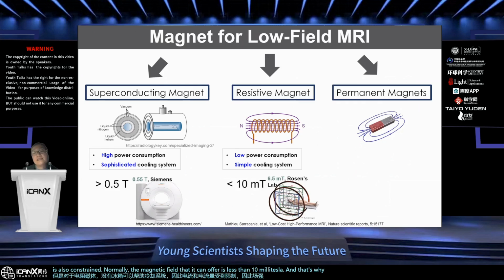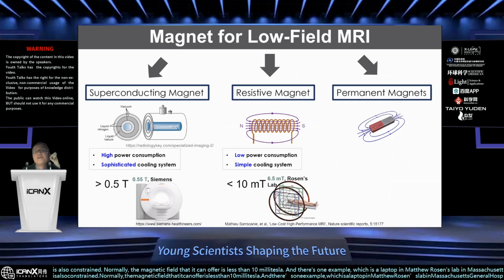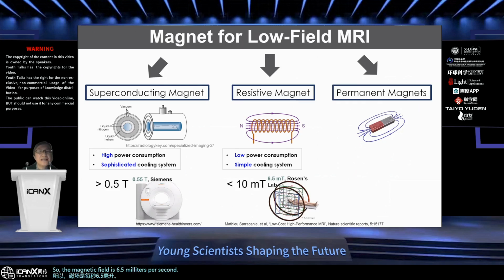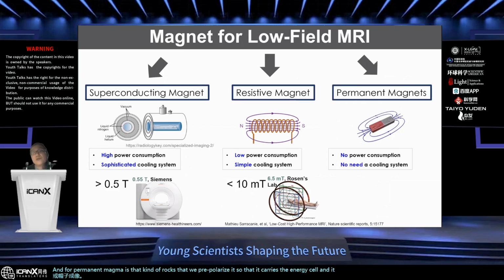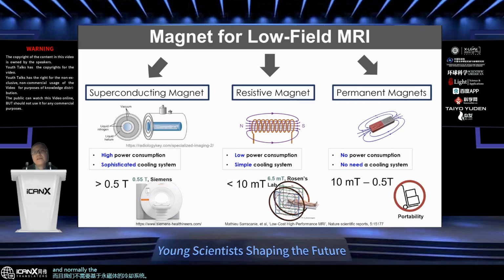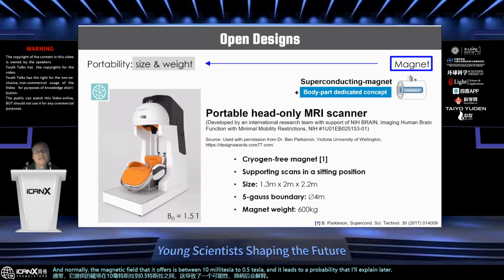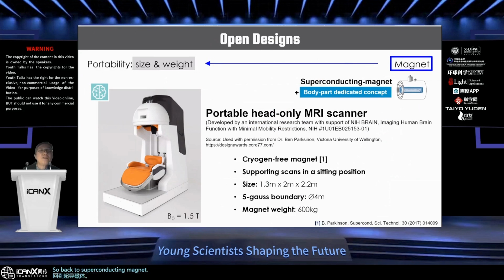There's one example, which is a lab setup in Matthew Rosen's lab at Massachusetts General Hospital. The magnetic field there is 6.5 millitesla for head imaging. A permanent magnet is that kind of rock that we prepolarize so that it carries the energy and the magnetic field. So there's no power consumption associated with it, and we don't need a cooling system for a system based on permanent magnets. Normally the magnetic field it offers is between 10 millitesla and 0.5 Tesla, and it leads to portability that I'll explain later.